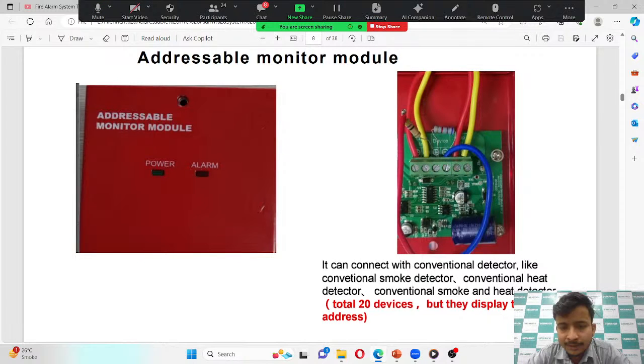You can connect up to 20 devices with this module, like 20 detectors in a loop with this module. But all the detectors will have the same address.